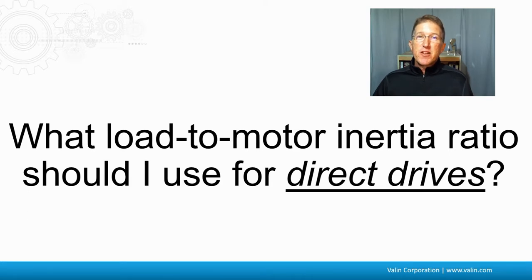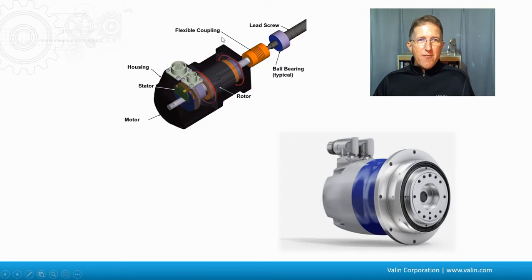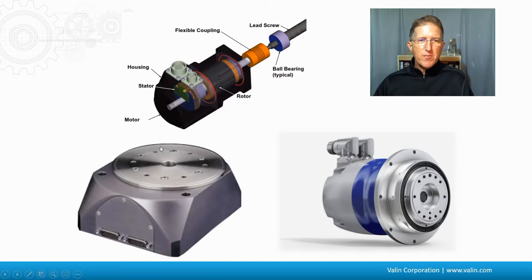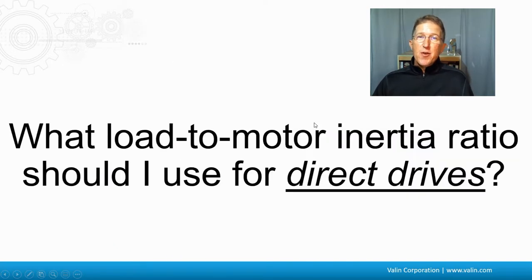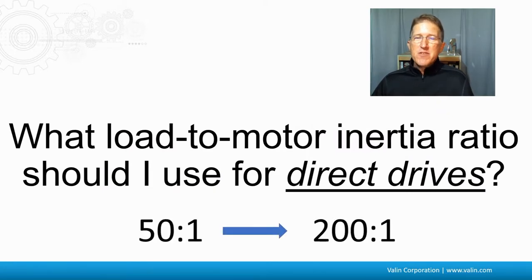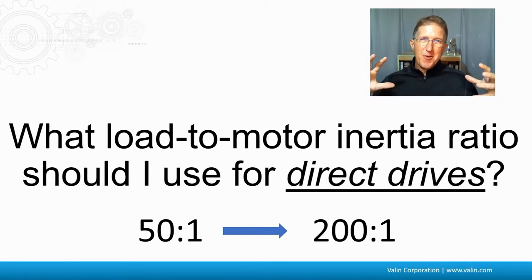For direct drive motors, motors are typically coupled to lead screws, belt pulleys, or other mechanics via flexible couplings that introduce some compliance. But if the motor has a flange front or is a direct drive where you can bolt the load directly to the motor, there's no compliance from a coupler. In that case, inertia ratios of 50 to 1, 100 to 1, or even 200 to 1 are acceptable, because the motor and load are essentially one rigid system with no compliance to tune out.